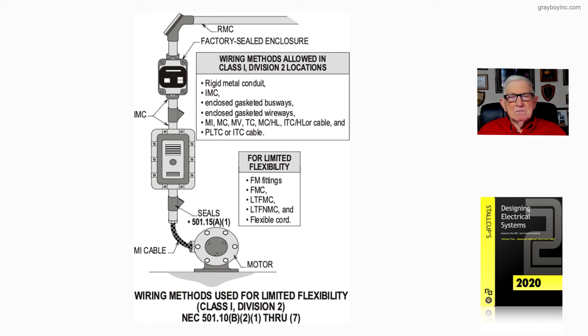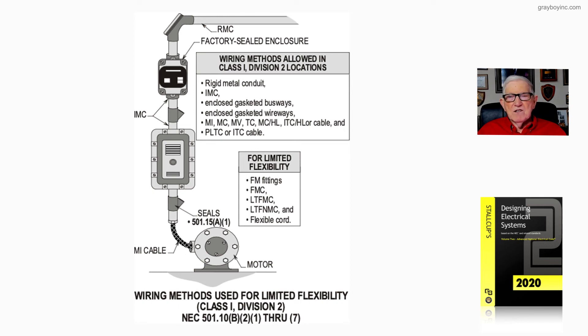MC, medium voltage, tray cable, MCHL cable, the ITC/HL hazardous location type cable, and PLTC or ITC cable. Notice there's quite a laundry list once you're in a Class 1 Division 2 location, but not so in a Class 1 Division 1 — you can't use some of these wiring methods because we're in a Class 1 Division 2 type location.